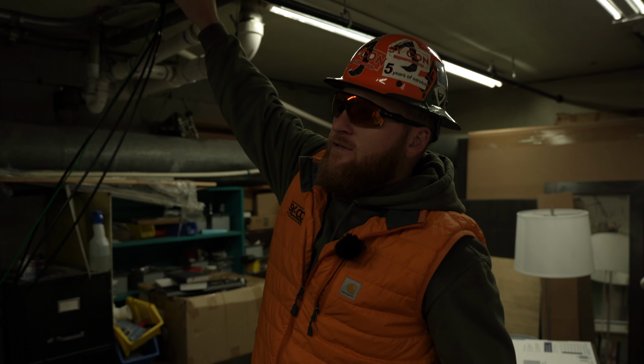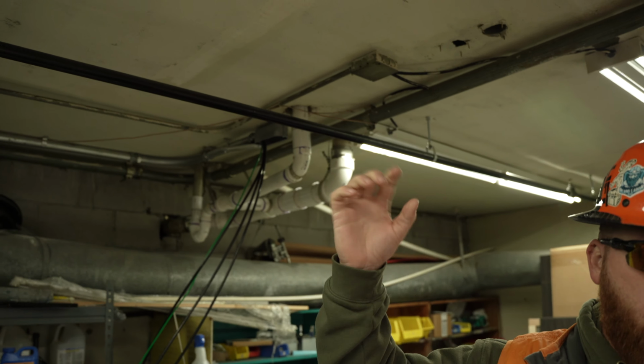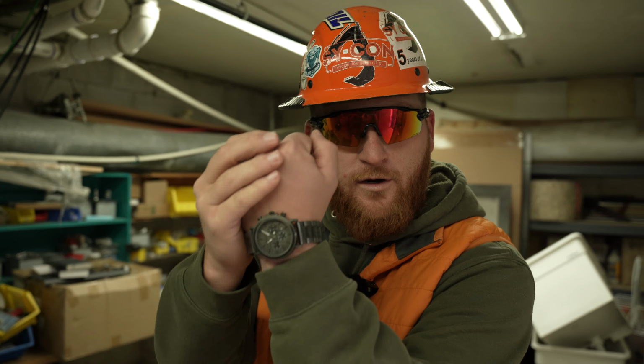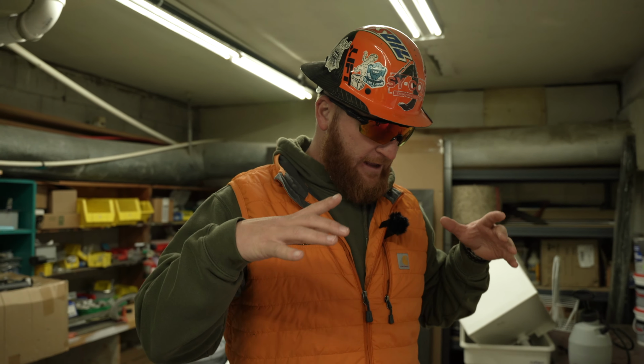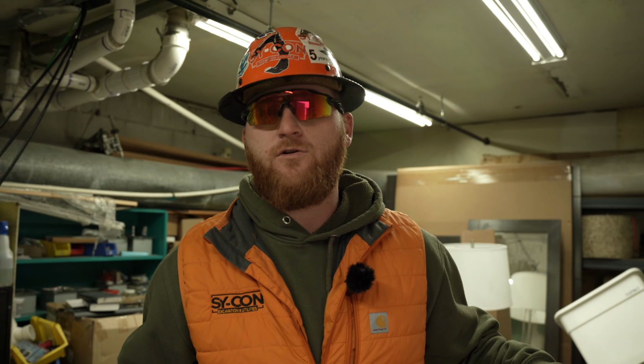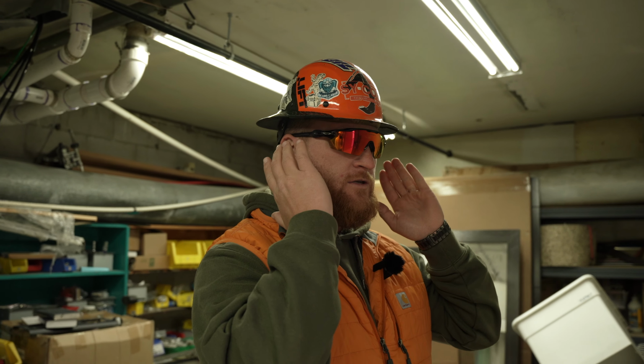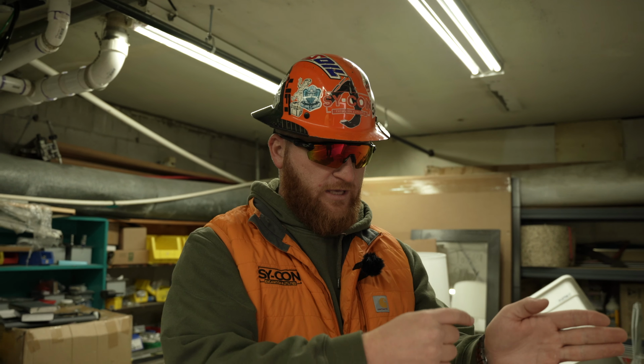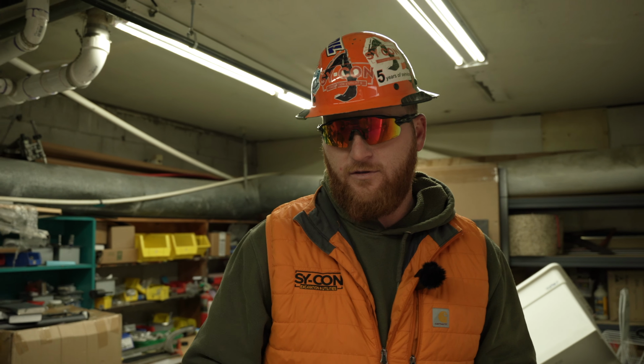Come here. They're going to bring fire suppression. When I say fire suppression, I mean this stuff right here that goes poof over your head if there's a fire. Sprinklers start. Well, you got to feed the water to them, eh? Here in Arkansas, we're a little bit different. It has to be a dedicated main directly just for your fire service for your commercial building. It can't be a 4-inch to feed the backflow, and you can't just pony off that fire line and run your domestic service, is what I'm trying to say.